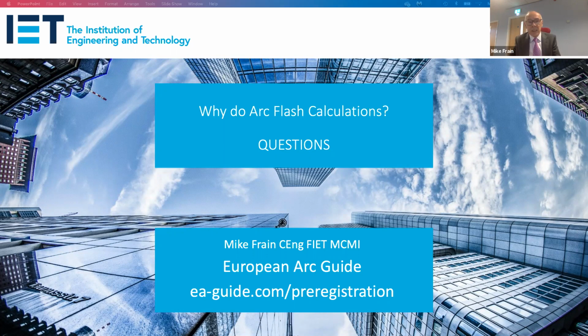If there's a fault on the equipment, I've seen situations — I can show you photographs — where a fault which has occurred on the load side of the incoming device has actually migrated to the line side. And that's in a Form 4 panel, by the way, a low voltage panel.